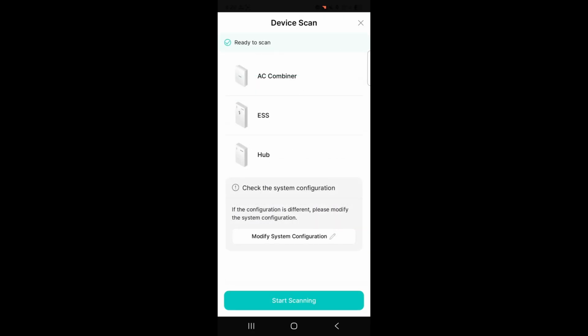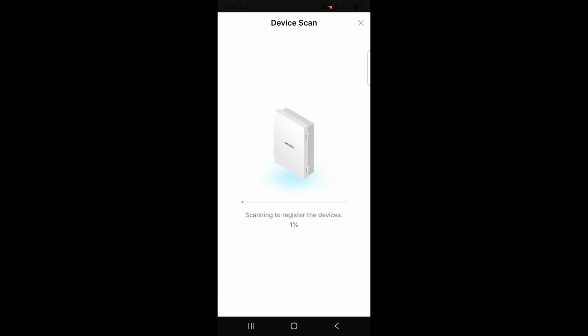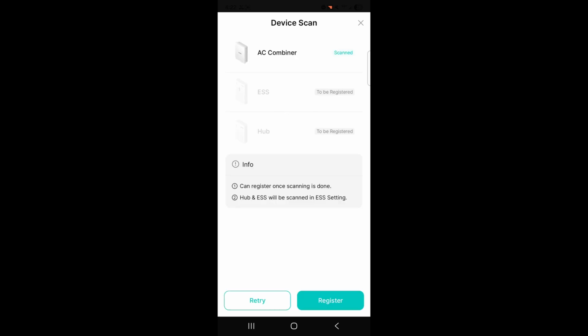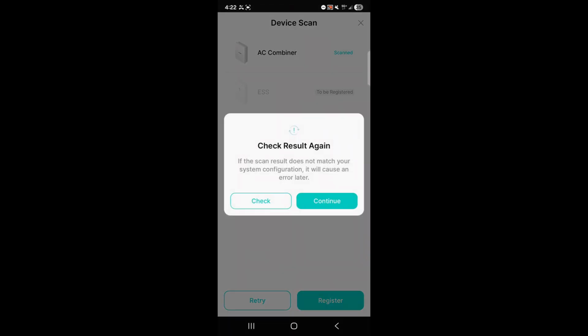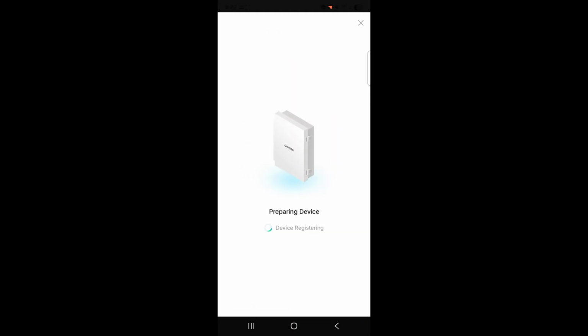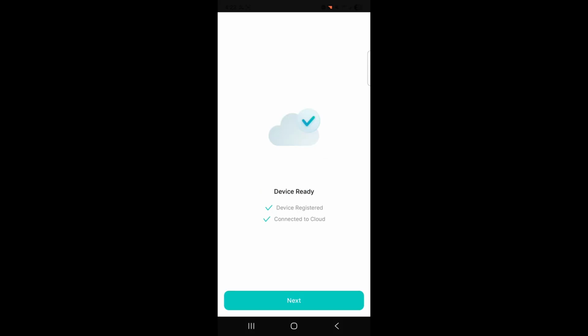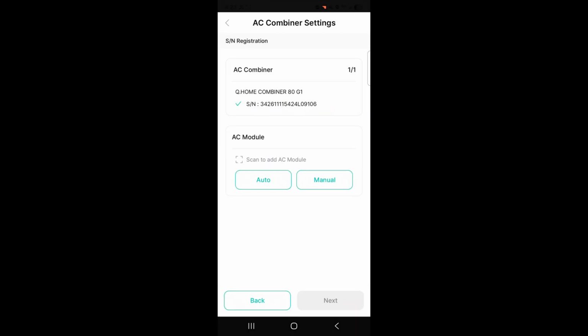Verify that the correct system components are displayed. If there is an incorrect component displayed, select Modify System Configuration to go back and make changes. Select Start Scanning to begin the automatic microinverter serial number scan. Once all components have been scanned, select Register. If the scan progress shows an error next to the AC combiner, click Check to retry the registration, or Retry to try scanning the combiner box serial number again.